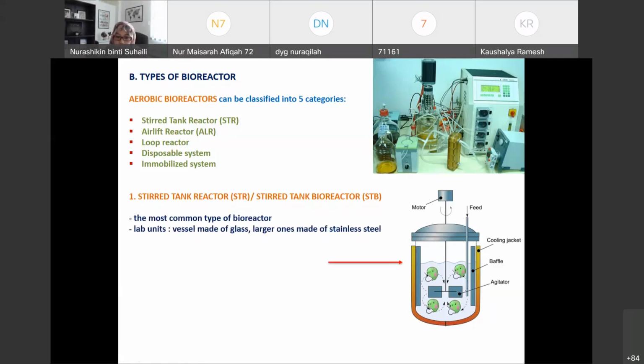It is the most common type of bioreactor, and it is made from two types of materials, glass or stainless steel. Normally the small ones, when I say small, maybe less than 10 liters, are made from glass, but it's a special kind of glass. It's not the normal glass. It's, I think, borosilicate glass, which means the glass is very durable and resistant to high temperature, because this vessel needs to be autoclaved, needs to be sterilized. When we autoclave, we apply high pressure. Glass that cannot resist high pressure will break. So this one is made from a special kind of glass.